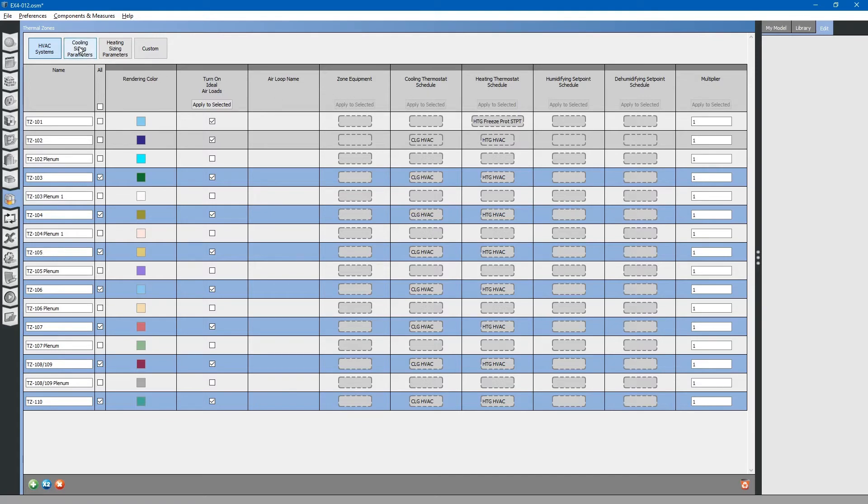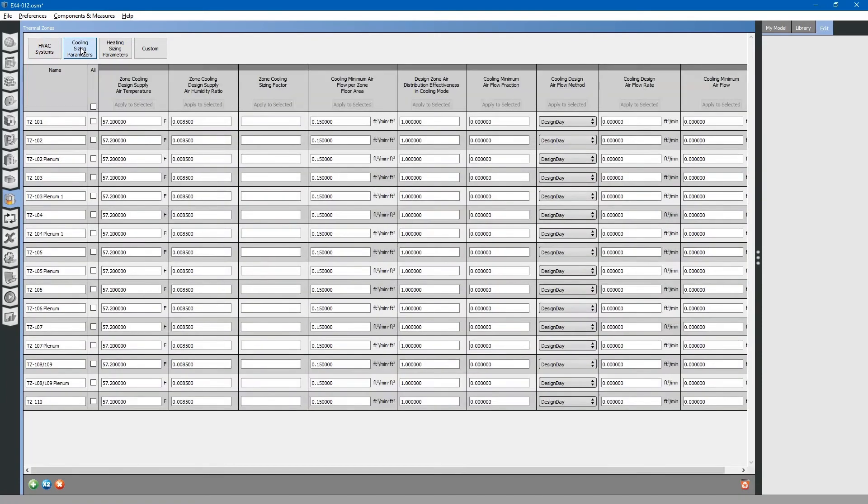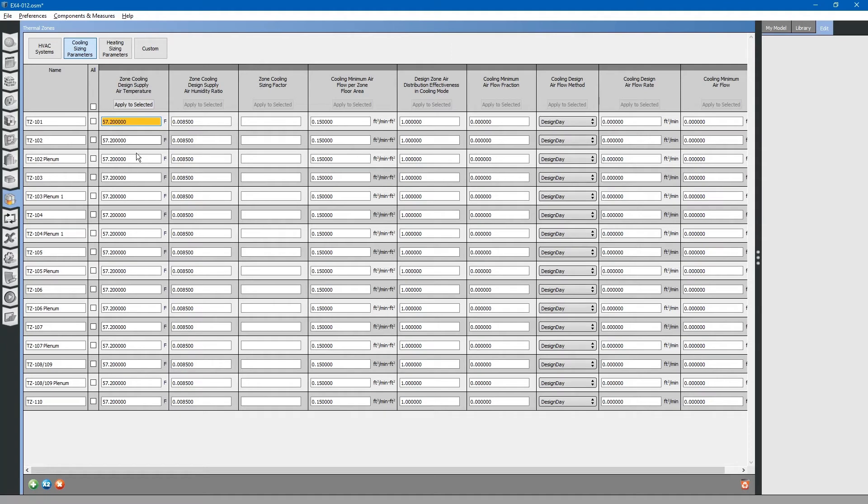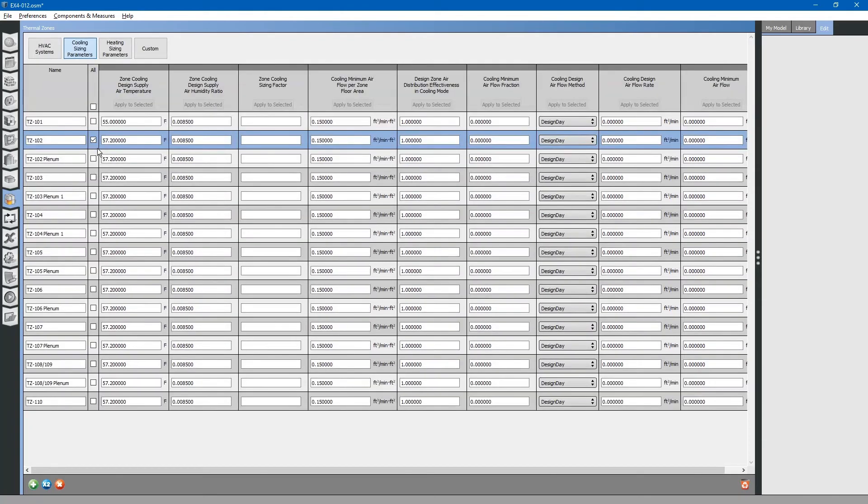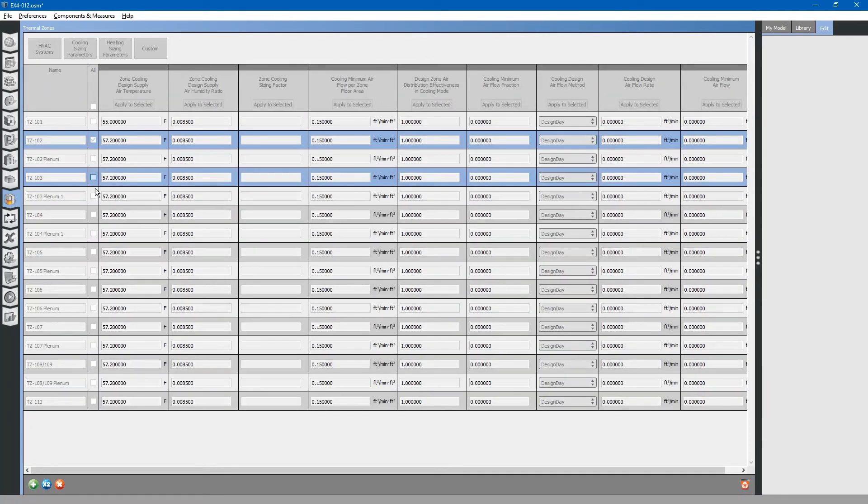Next, we can go to the cooling sizing parameters button at the top. The first column is zone cooling design supply air temperature. You may want to edit these based on local comfort standards. I normally do 55. You can apply these to the other zones.